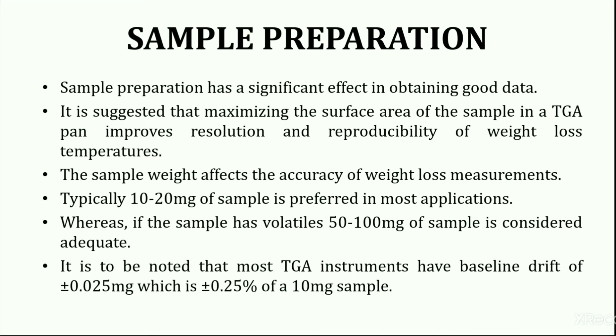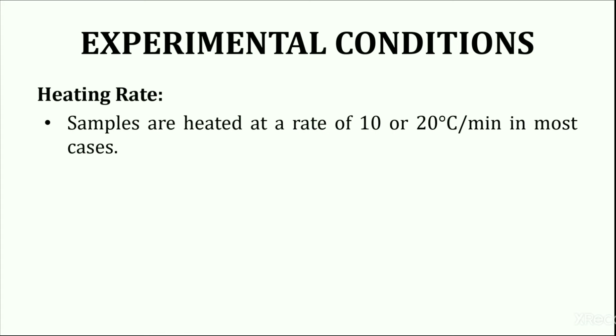During the calculation and preparation of the result, a baseline drift value of plus minus 0.025 mg is considered for accuracy and precision purposes. This drift value is around plus minus 0.25% of the 10 mg sample. During the experimental procedure, samples are heated at a rate of 10 or 20 degrees Celsius per minute in most cases. However, lowering this heating rate improves the resolution of overlapping weight losses. Modern TGA instruments are very advanced and use an automatic temperature control unit to improve the resolution of the instrument. This temperature control unit automatically reduces the heating rate during periods of sample weight loss.